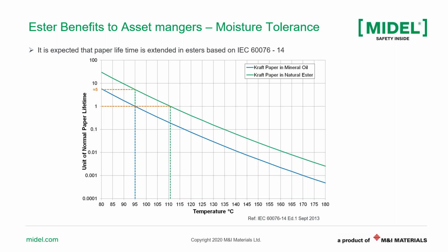This is taken from the IEC 60076-14 for high temperature insulation material. On the x-axis, you see the operating temperature, and on the y-axis, you see the unit of normal paper lifetime. 1 here means that the paper will live its expected lifetime, say 20 years. And on this chart, you see two graphs, one in blue and one in green. You have the kraft paper in mineral oil, the blue one, and the green one, the kraft paper in natural ester.